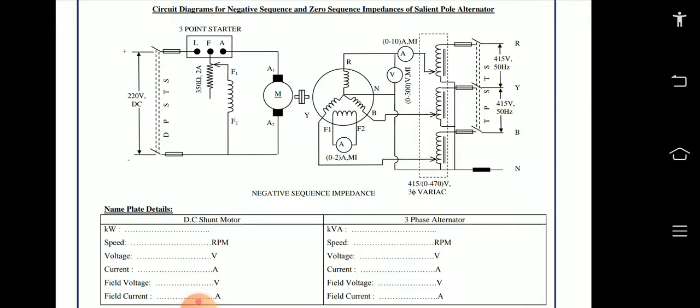The negative sequence current produces an armature reaction which rotates around the armature at synchronous speed in the direction opposite to that of the field poles, so it rotates past the field poles at double synchronous speed. This induces current in the field, damper winding and rotor iron. The impedance encountered by the negative sequence current is called the negative sequence impedance of the generator or alternator.